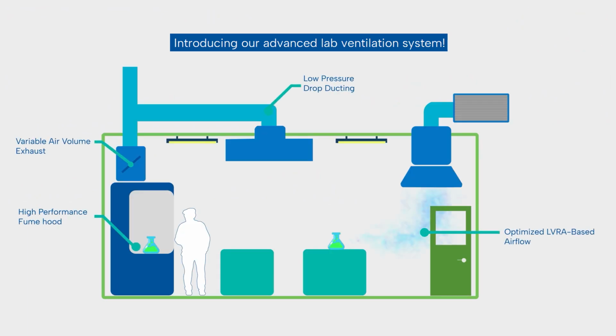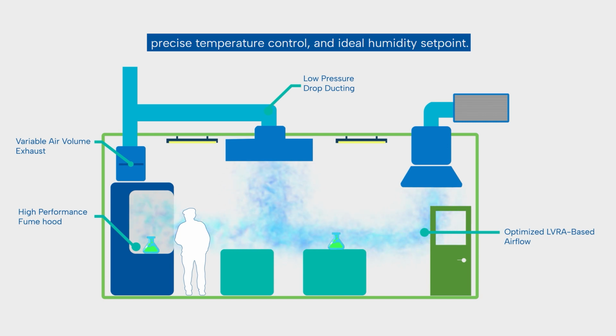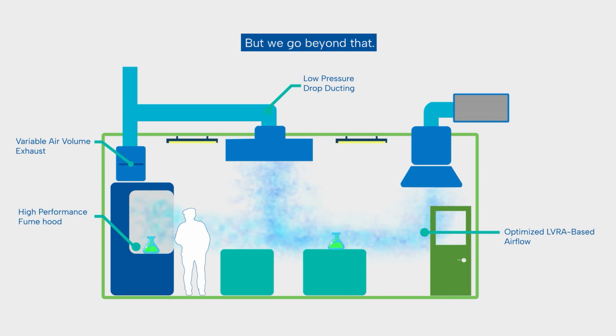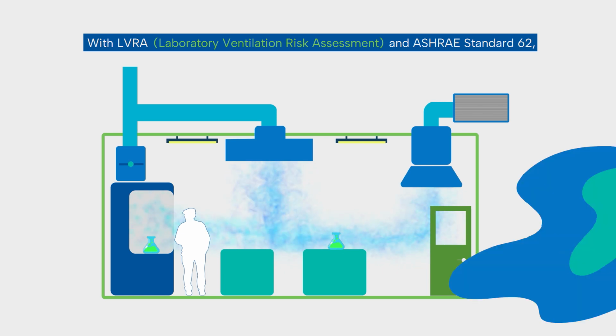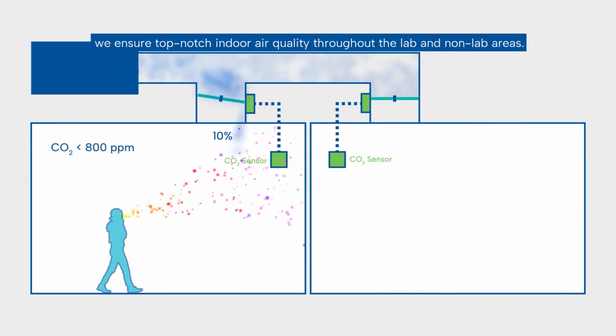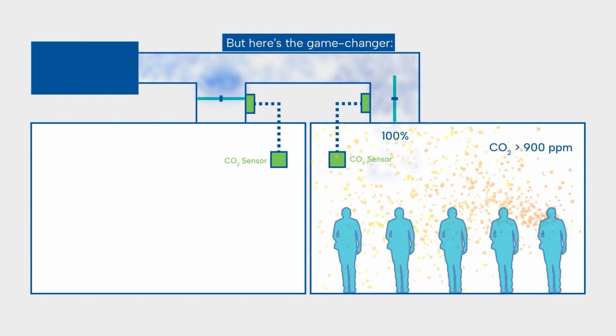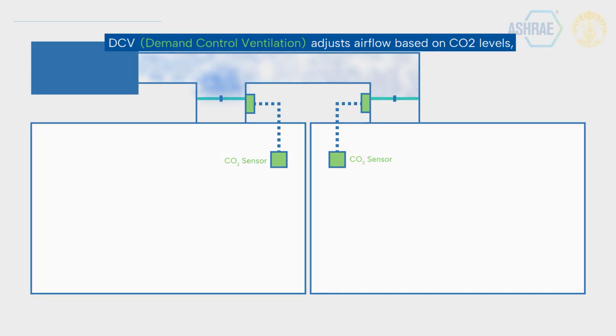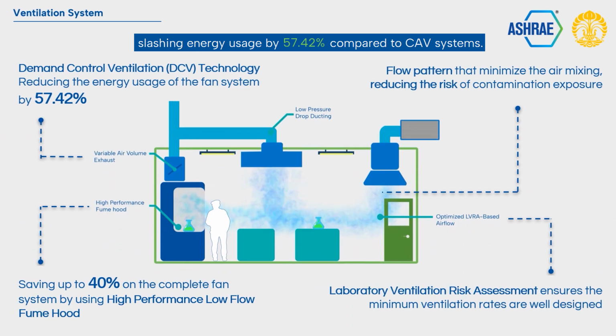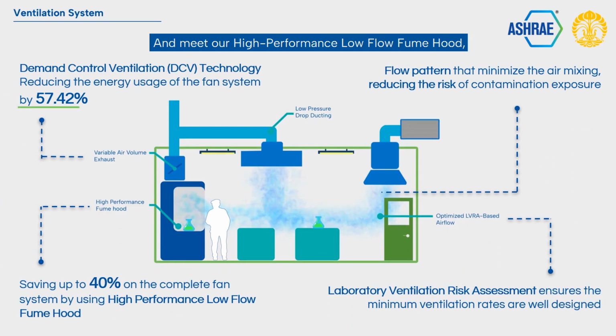Introducing our advanced lab ventilation system, it starts with the ASHRAE minimum ventilation rate, precise temperature control, and ideal humidity set point. But we go beyond that. With LVRA and ASHRAE Standard 62, we ensure top-notch indoor air quality throughout the lab and non-lab areas. But here's the game changer. DCV adjusts airflow based on CO2 level, slashing energy usage by 57% compared to a CAV system, and meets our high-performance low-flow fume hood that cuts energy consumption from the fan system by 40%. With adherence to ASHRAE Standard 170 and 62.1, our system customizes ventilation for your lab's needs while keeping occupants comfortable.